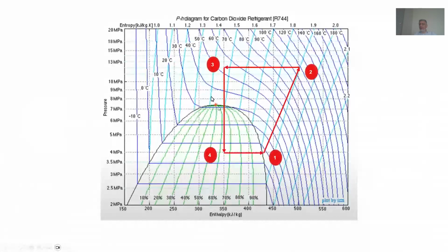and then it goes back to the cycle. So this is a typical cycle where your compressor does the work, you do a heat exchange using water coming from the source, and then you do expansion and go back to the compressor. If your water is coming in around 55 degrees centigrade, that will be the energy you can extract.